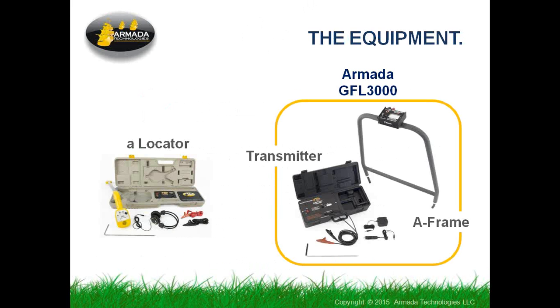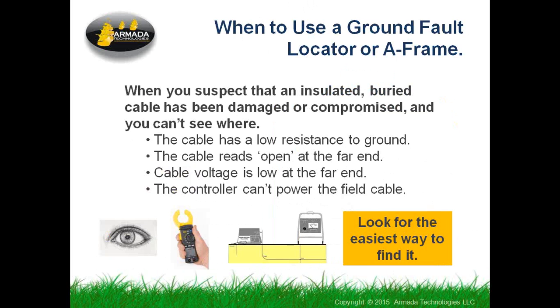So the equipment we're talking about today is the ground fault locator, and we're using the Armada GFL 3000 as an example. This kind of pulsed technology, you may know under names like the A-frame, the pulsar, ground fault locator, is a technology pioneered originally by Radiodetection, and you may have also seen a device similar to this from Progressive Electronics or Armada and Greenlee. So if you have any of these devices, you can follow these very same techniques, really, because they all follow the same piece of technology generally. You need to have a locator as well, because the ground fault locator is not very much use if you don't know the path of the cable you're troubleshooting. So you always have to have the path of the cable located. This is critical to accuracy.